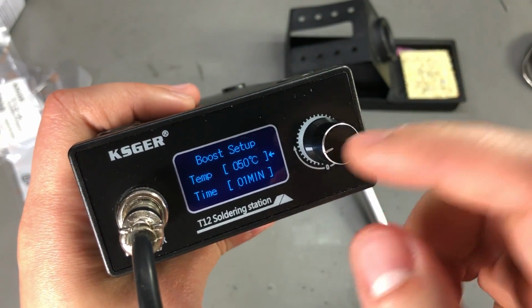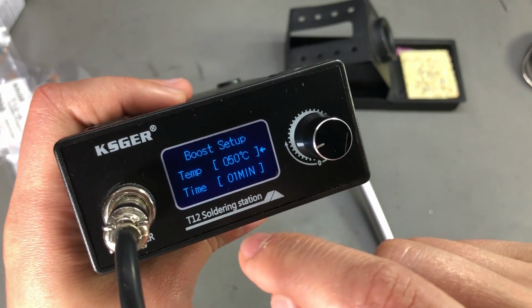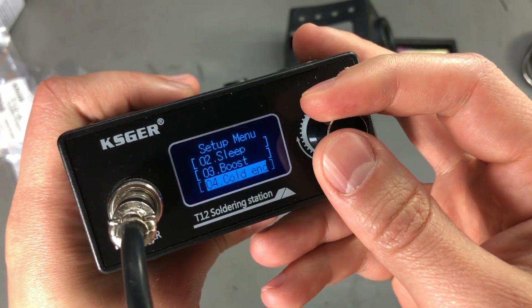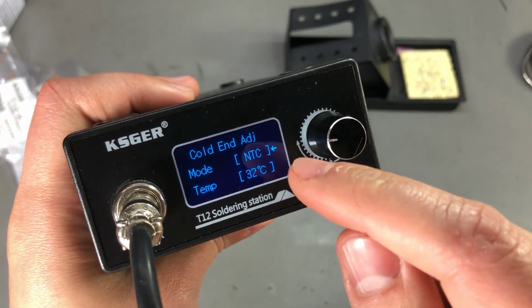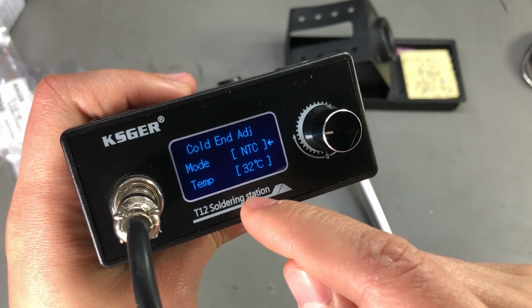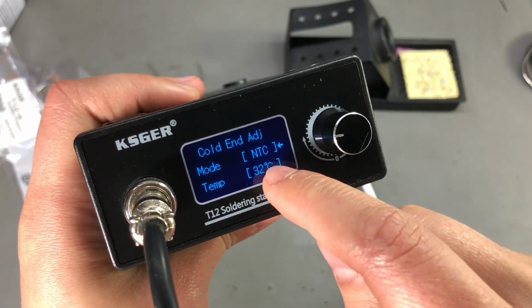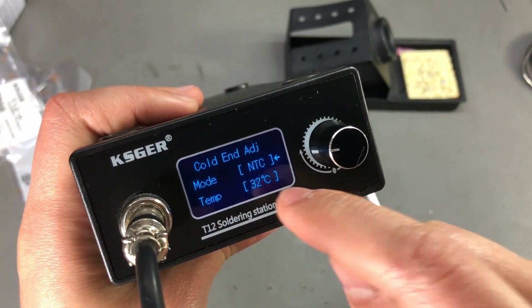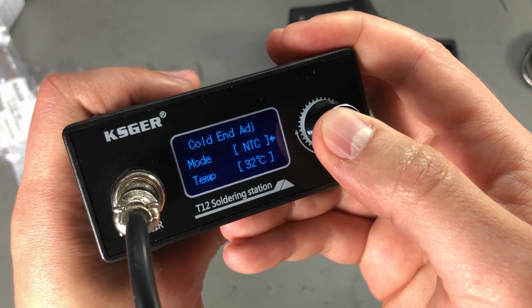These are the boost settings, so it will boost the temperature by 50 degrees for 1 minute. This is for cold junction compensation—we have an NTC installed, and we can compensate for its temperature if it's not measuring accurately.